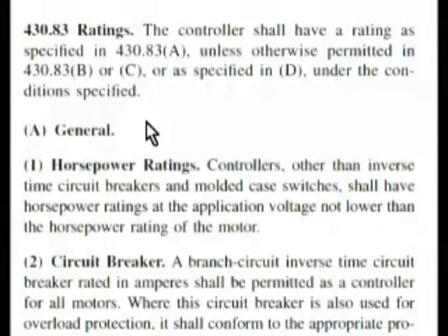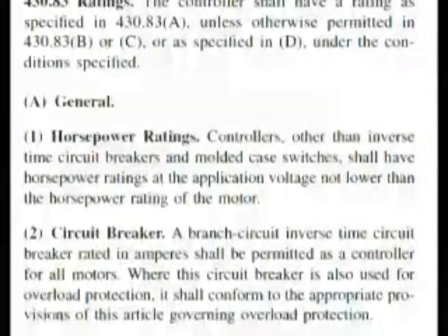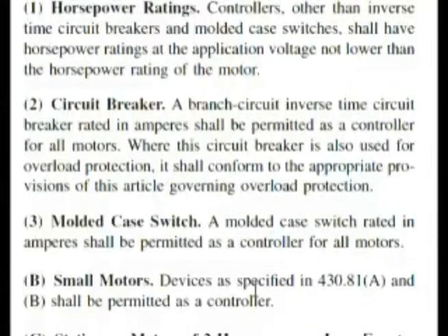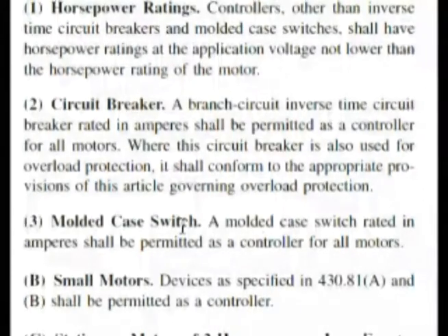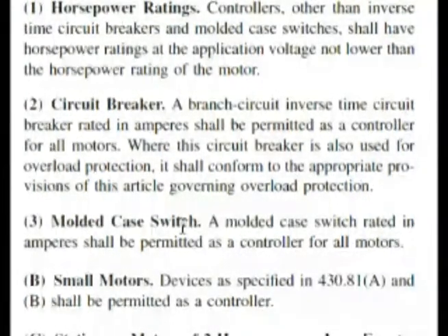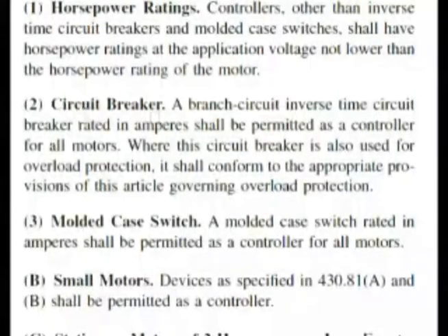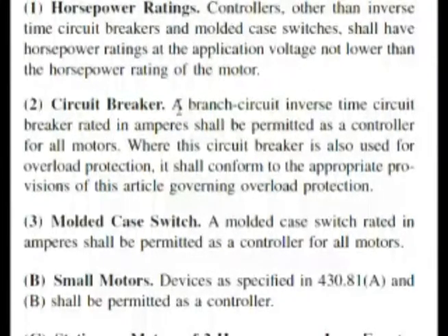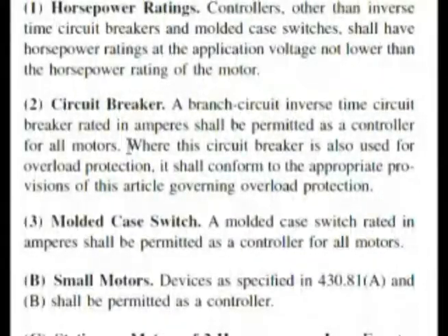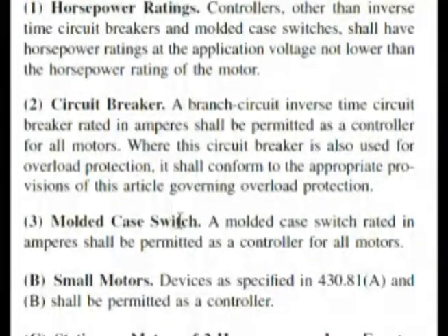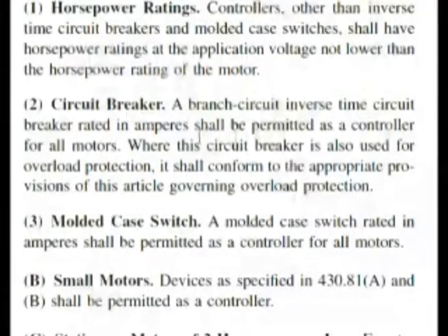As we kept going down something jumped out — molded case switch. That was choice B. And it said a molded case switch rated in amperes shall be permitted as a controller for all motors. However, if you go up here, it says circuit breaker — a branch circuit inverse time circuit breaker rated in amperes shall be permitted as a controller for all motors. That was also one of our choices. It would have been easy to read just the one and miss the other.